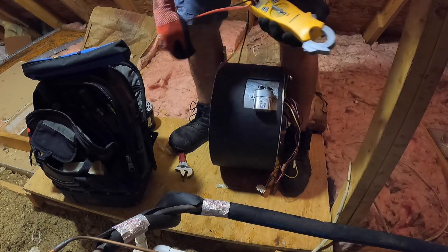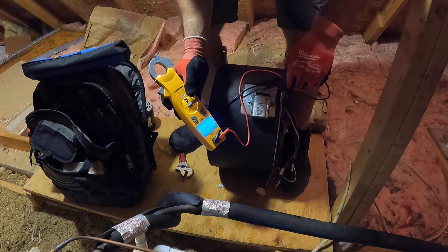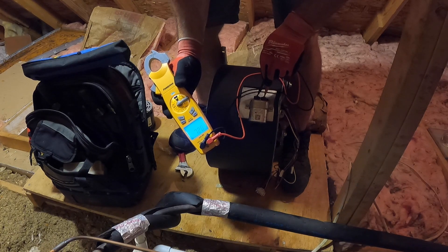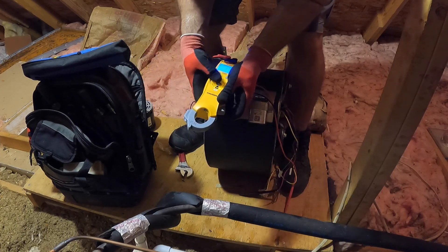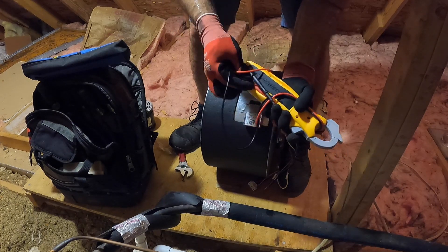This is a seven and a half microfarad capacitor with a five percent tolerance. Got my new clamp meter out, set it to microfarads — reading 7.29. Hey Siri, what's 95% of 7.5? 95% times 7.5 is 7.125. So we're within the tolerance. Because it has a 5% tolerance, that means it can be as low as 95% of its rating or as high as 105%.